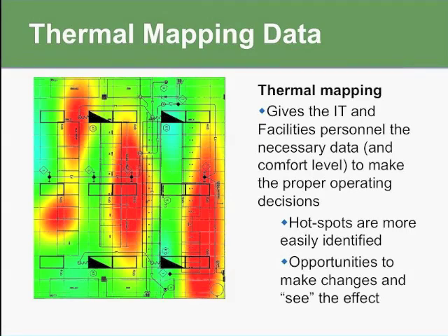I'm reducing the speed of the fans slowly, making sure we don't get the hot spots. And you can even raise the set temperature of the CRAC units, and make sure that you don't run into problems. But right now, you can easily identify where and when you have hot spots, and you can make changes to either perf panels or blanking panels, and make sure that you're getting the performance that you think you're going to get. So basically, it's data, and more data.